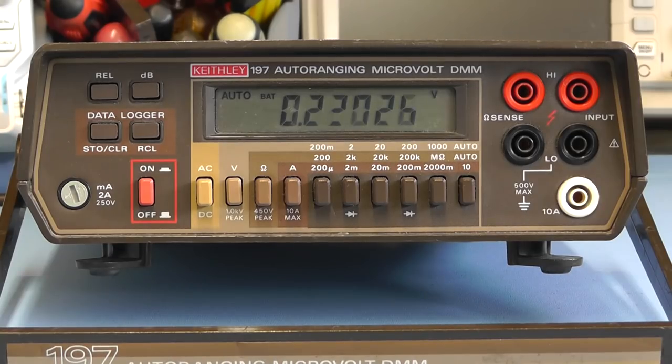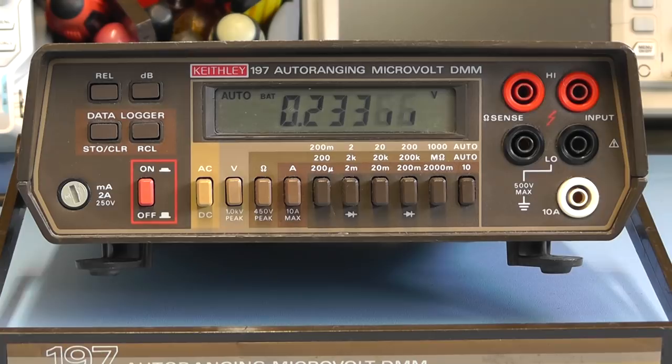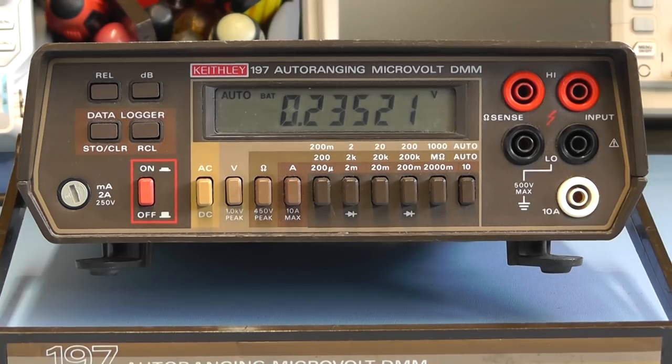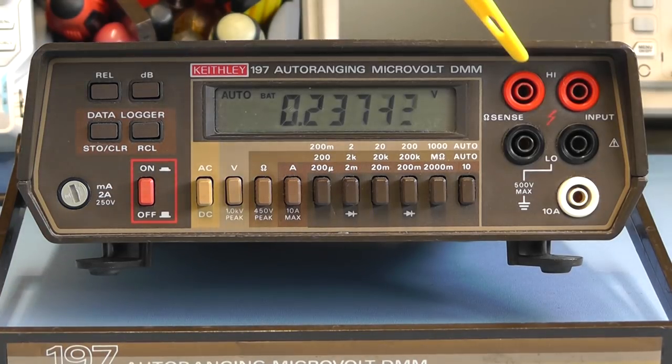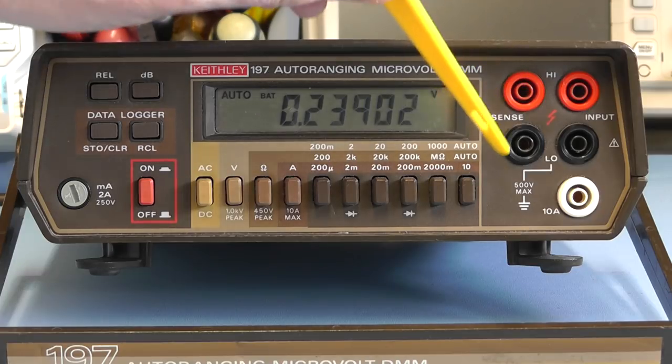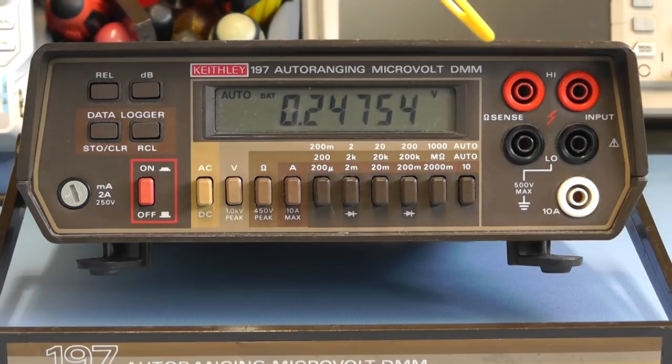Before we take the case off this meter I should just point out one other main difference between this and the Keithley 175 and that is it has two additional input terminals here which are used on the Ohms range and these are the Ohms sense terminals and they provide for a four wire resistance test with this meter and improve the accuracy.